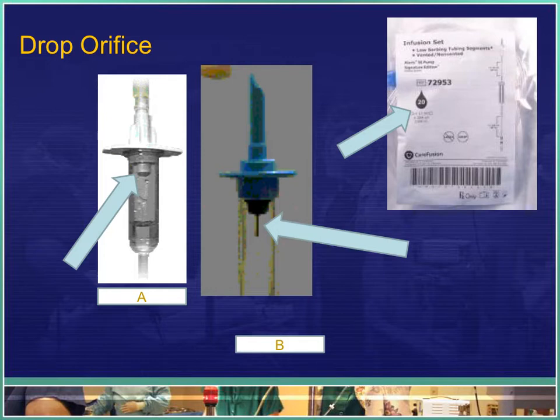The micro drip delivers a smaller drip, and there's only one type. It's the drop factor of 60, which means it takes 60 drops to make 1 mL. The figure on the far right is pointing to the number 20 as a drop factor. So that infusion set is illustrating a 20 drop set.